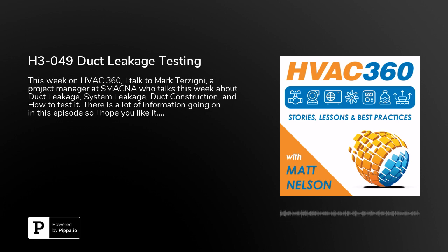Now, I guess something that goes along with pressure classes is the seal class. Can you explain that and how that relates to the pressure class? Sure. There are three things that I'll mention that are sometimes misconstrued, confused, or mixed together. One is pressure class, which we already covered, which is how you fabricate the duct based on the static pressure we expect it to operate at or below.